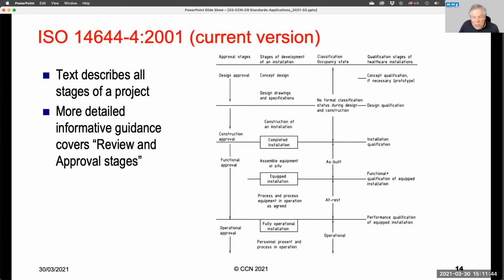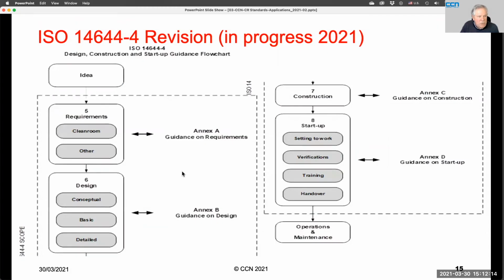So Part 4, 2001, is pretty old now, 20 years old, and it has this rather simplified diagram of the stages of a project from concept through to fully operational, going through various stages. And in here is included the concepts of qualification and validation, particularly in the healthcare sector, that are identified here. Now, in the revised version, that's refined somewhat and becomes a little bit more sophisticated and I think a bit better organized. So there's a flowchart diagram that starts off with the need and requirement, goes through defining the detailed requirements, URS, the design process, construction of the installation, startup, including commissioning and verifications, which you could read into our qualification activity, and then ultimately into operations and maintenance.